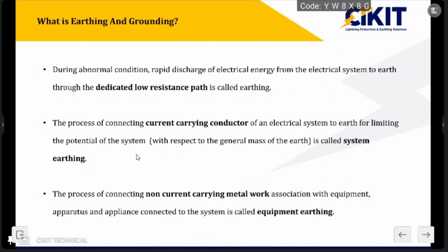So why earthing is important, and how the earthing for a substation is different from the earthing we provide for other applications. Earthing is nothing but providing a dedicated low resistance path for either the fault current or impulse current to discharge into the soil. At normal operating conditions, there won't be any need for discharging this current. So earthing comes into the picture when there are abnormal conditions like a fault condition or lightning impulse passage conditions.